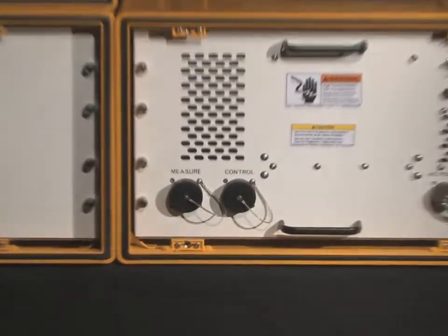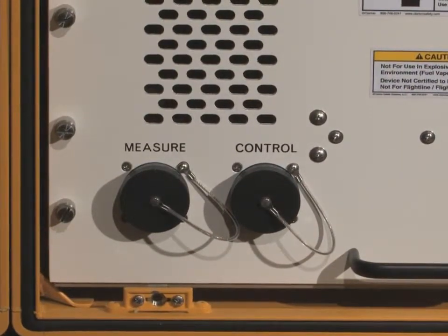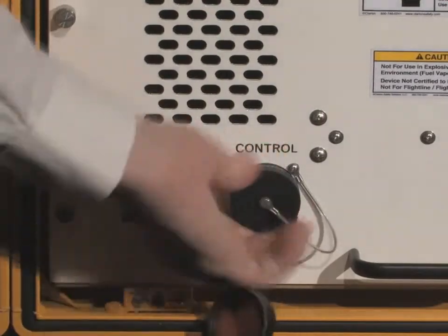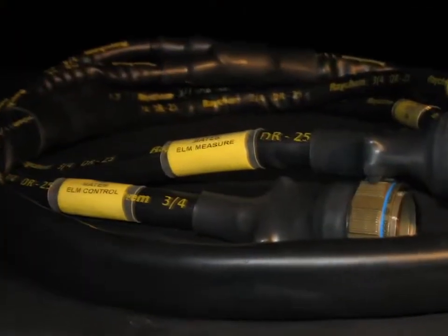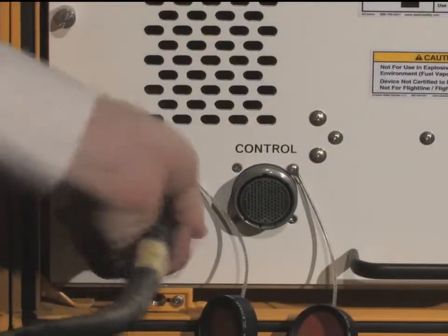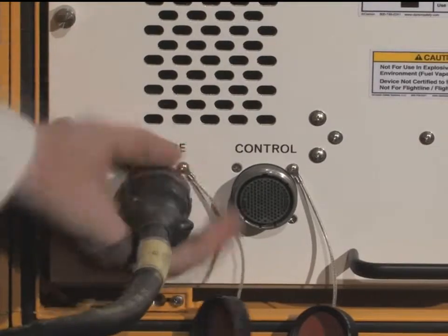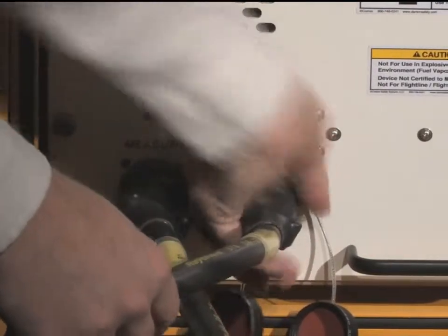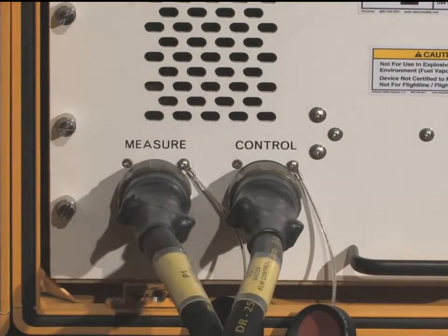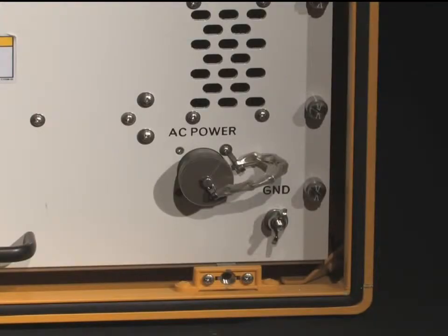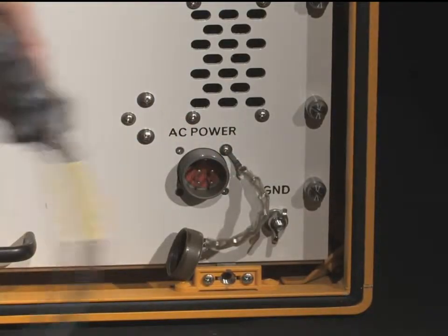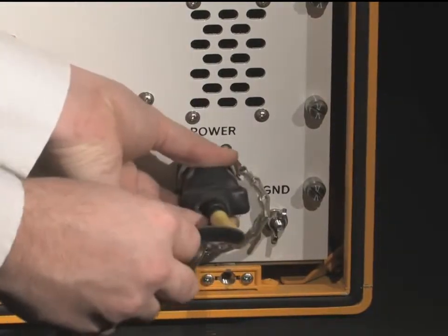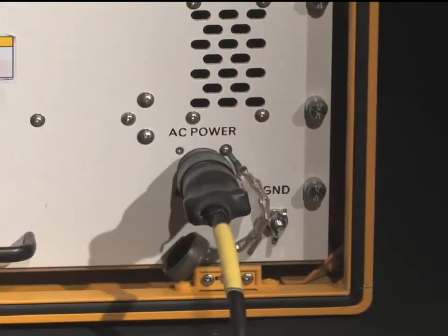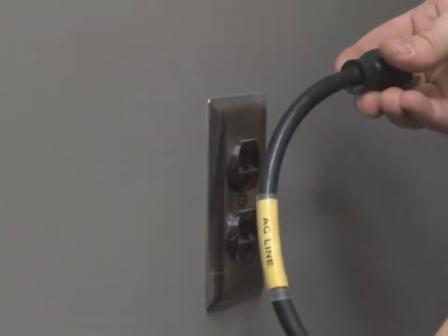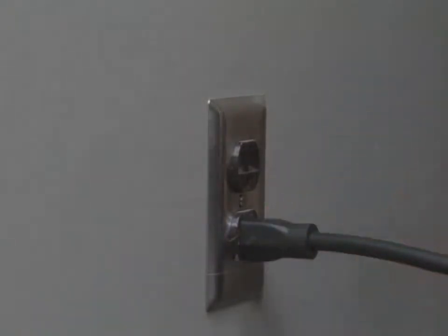Next, locate the measure and control connectors on the rear panel of the external load module and unfasten their dust caps. Connect the P1 measure and P2 control ends of the external load module interface cable to the respective measurement and control connectors on the rear panel of the external load module, being sure to key the cable connectors properly. Next, locate the AC power connector on the rear of the external load module and unfasten the dust cap. Connect the external load module AC power end of the AC input cable to the AC power connector. Connect the AC line connector of the cable to a standard wall outlet.